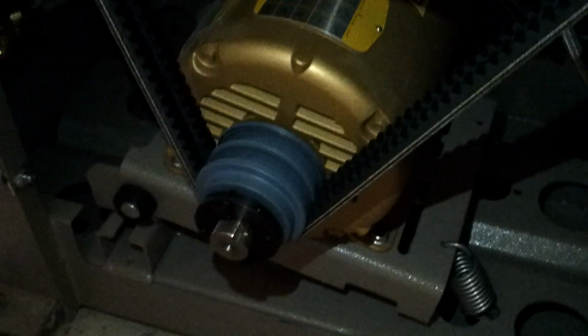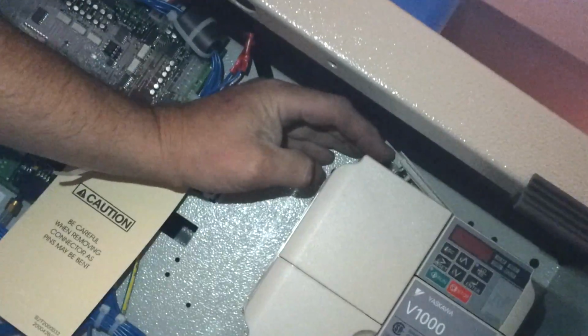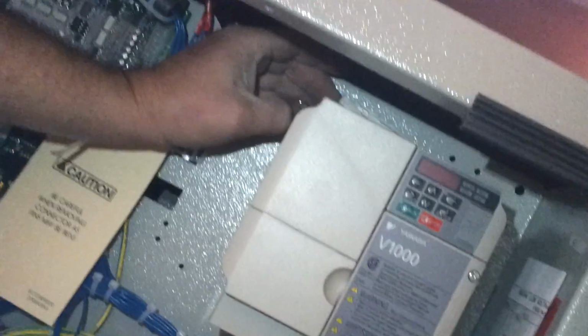Now you want to make sure that these cooling fins that are on the motor don't get a lot of lint or dirt or any kind of buildup. So you might want to take a small painter's brush or whatever and just brush those out. Keep that clean. And then also on top here you have your inverter, and there's a little fan that's right here. You lift this cover up and you'll see a little fan in there. When you check your oil, change your oil, check to make sure that your fan is running.